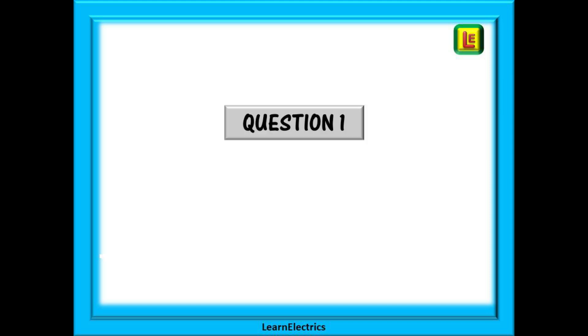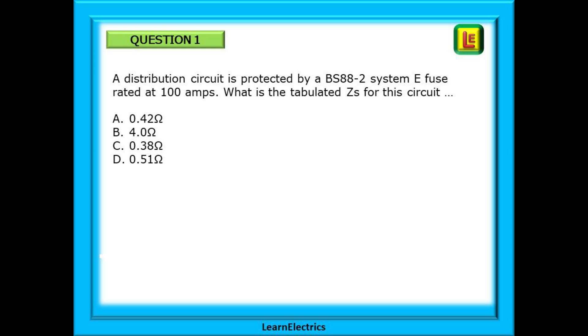Let's begin with question 1. A distribution circuit is protected by a BS88-2 system E fuse rated at 100 amps. What is the tabulated ZS for this circuit? Pause the video and find the answer. You should have answer A, 0.42 ohms and the box shows you the route to the correct answer.